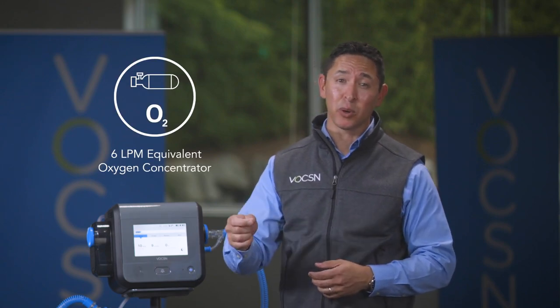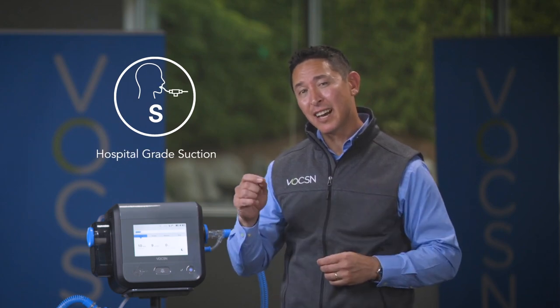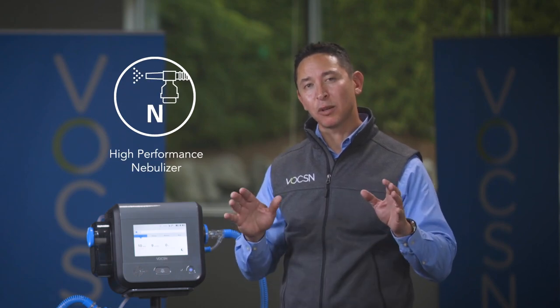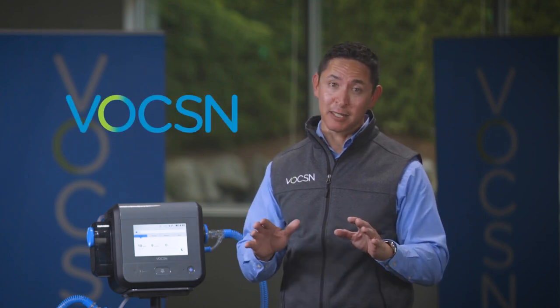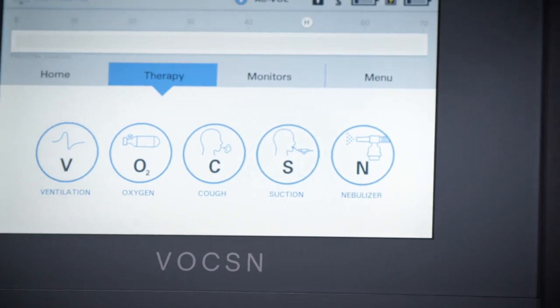VOCSN is a unified respiratory system that combines a critical care ventilator, an oxygen concentrator that can deliver up to six liters of flow equivalent, cough assist at the touch of a button, hospital-grade suction that provides consistent high flows, and a high-performance nebulizer that will automatically sync with the flow from the ventilator and turn off once the therapy is done. VOCSN is fully customizable — if a patient doesn't need one of the therapies, they don't have to have it. VOCSN was designed from the hospital to the home, and for patients five kilograms and above.